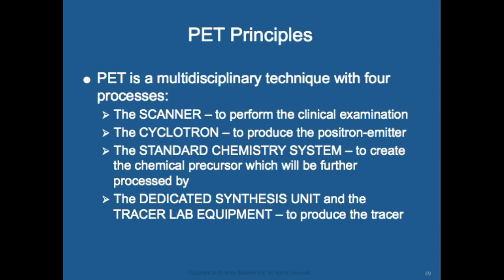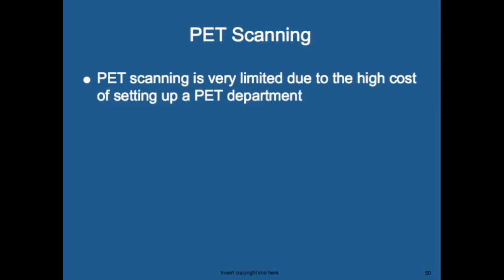The standard chemistry system creates the chemical precursor, which is further processed by a dedicated synthesis unit and tracer lab equipment to produce the tracer — all of this is required for PET imaging. PET scanning is very limited due to the high cost of setup, which is why you see mobile PET trucks visiting hospitals once or twice a week to scan all patients.